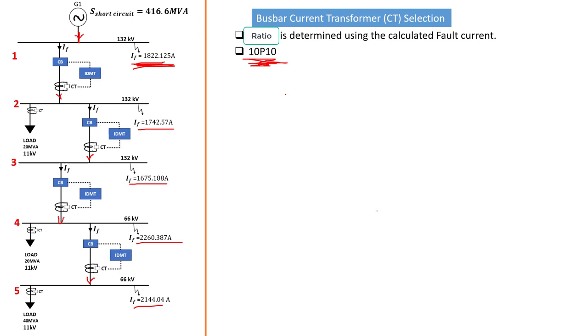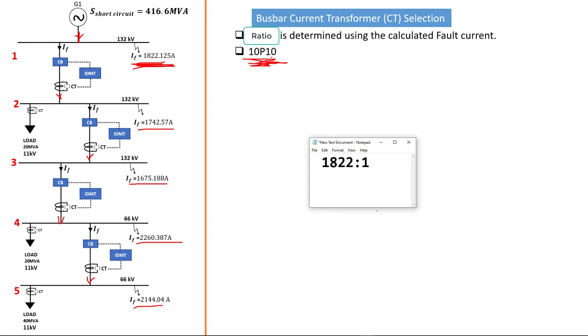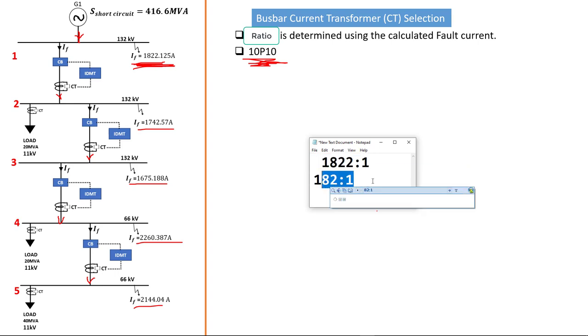The 10% means the measurement we're going to get at the secondary will be plus or minus 10% of the actual representation. The other 10 means that our rated primary current must be multiplied 10 times — it's 10 times the rated current. So instead of having a ratio of 1,822 to 1, the 10 will divide the rated current by 10 to give us 182 to 1. That way you can get a smaller current transformer rather than a big one with all these turns ratios.